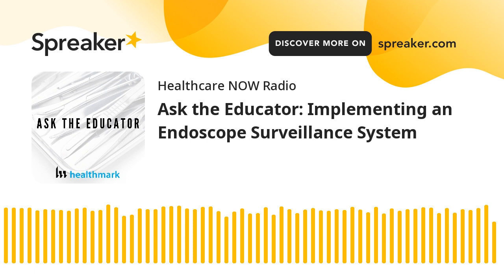The history as to why microbial surveillance has come up is related to the reports that we saw many years ago, back to 2012 and maybe even before that, about reports of infection related to contamination remaining on endoscopes after they've been reprocessed. So we saw many of those outbreaks, or superbug outbreaks, as we called them, starting in that time period and continuing for a couple years. And then the first safety alert that we got from the FDA was in August of 2015, where they recommended supplemental measures that enhanced duodenoscope reprocessing. So really risk mitigation strategies to be used when reprocessing duodenoscopes. And the first one on that list was culturing.